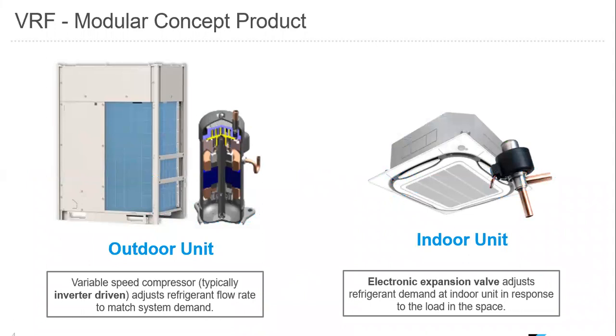So let's talk a little bit about the different components within a VRF system. Like I said, we're a very modular product. We consist of an outdoor unit. That outdoor unit has an inverter compressor inside of it. An inverter compressor, think of a VFD. Imagine you have a VFD on a fan. That VFD allows that fan to speed up and speed down. The inverter compressor does the same thing inside a VRF outdoor unit. So we're able to speed up and slow down that compressor.